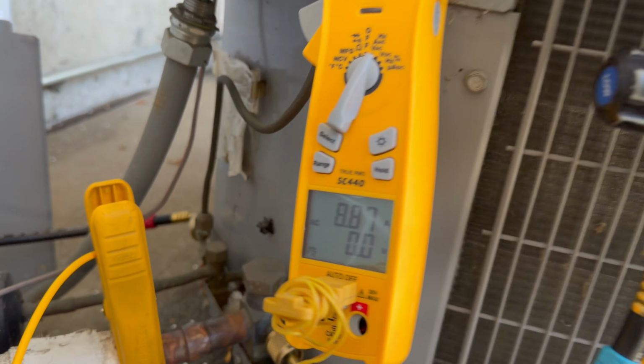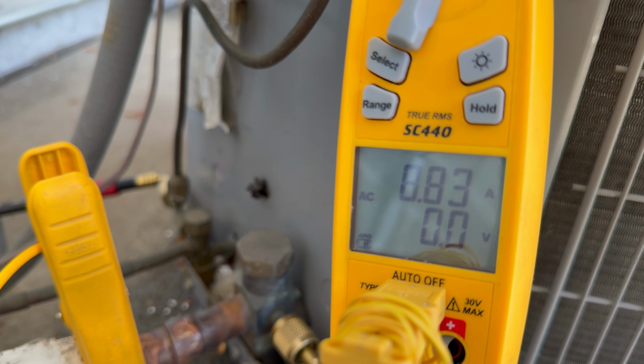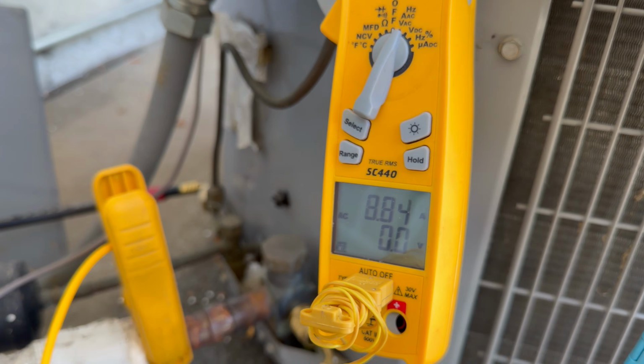Subcooling 15 degrees. Compressor amps have dropped just a little bit, 8.8 compared to 9.1. So overall, washing these dirty condenser coils did make a difference. Even though it is a very slight, minute difference, over time, that adds up.